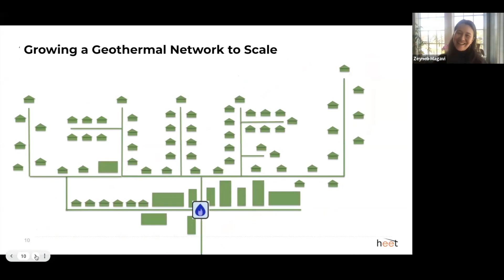Just to give you a sense of the scale of this, and there are more case studies than this one, but I love sharing this one: there's 2.5 miles of central loop pipe, 8 separate borehole fields, 427 boreholes, around 1,000 heat pumps distributed around all these buildings. They have additional attachments of cooling towers and gas boilers that are there for backup. The boilers have not fired once, have not been needed to cover or back up the network geothermal. The cooling towers have been used only for very hot days.